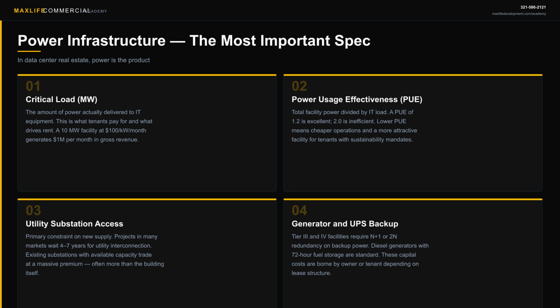Second is power usage effectiveness, or PUE. This is total facility power divided by IT load. A PUE of 1.2 means for every dollar of power going to servers, you are using 20 cents on cooling and overhead. That is best in class. A PUE of 2.0 means you are wasting as much power cooling the building as you are running the computers. Tenants care deeply about this, especially those with ESG commitments.